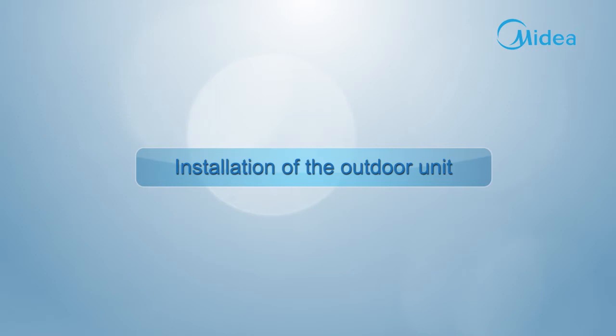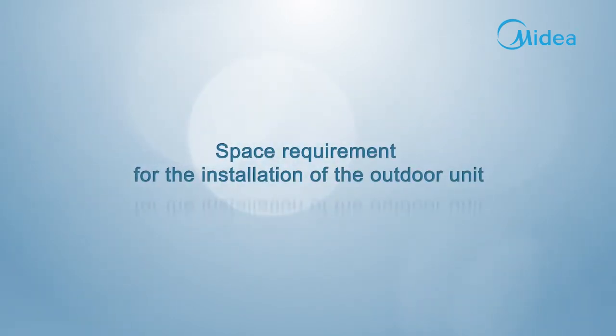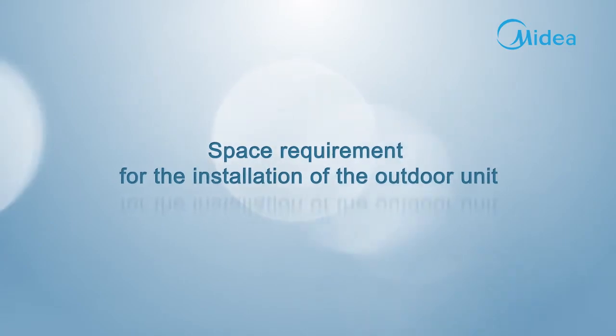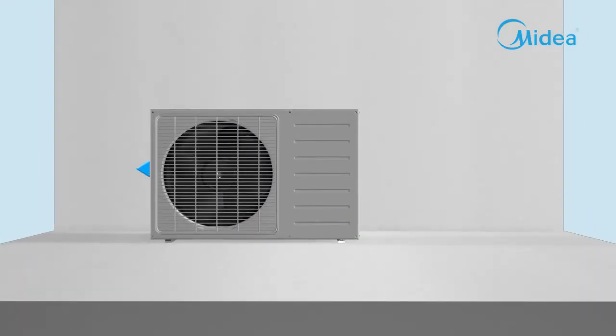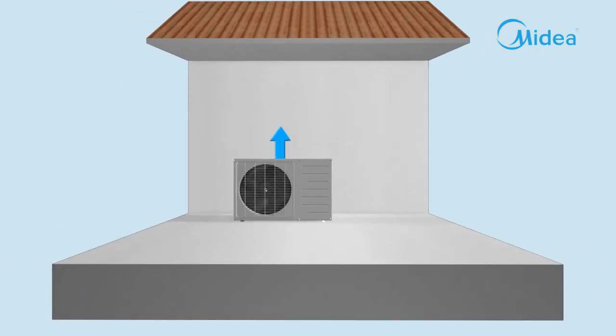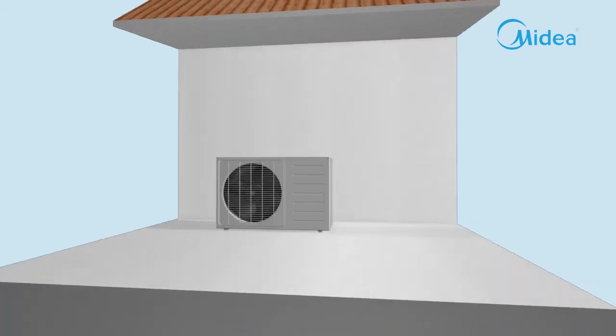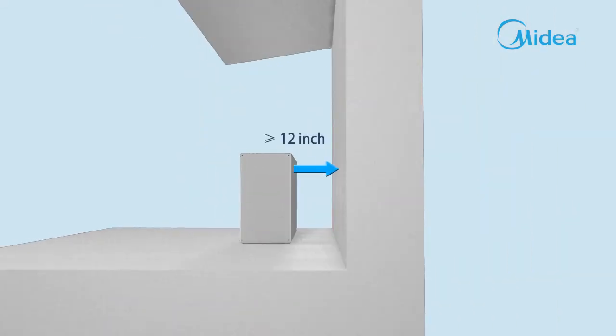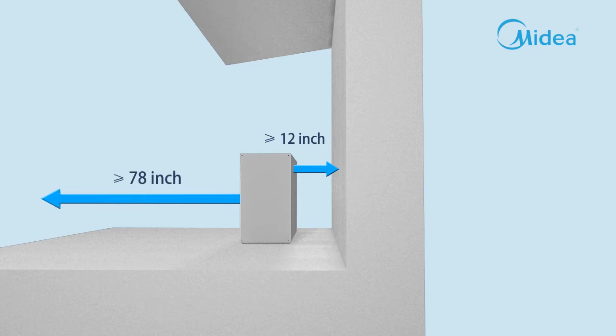Installation of the outdoor unit. Space requirements: no less than 12 inches for left space, 24 inches for right space, 24 inches for upper space, 12 inches for back space, and 78 inches for front space.